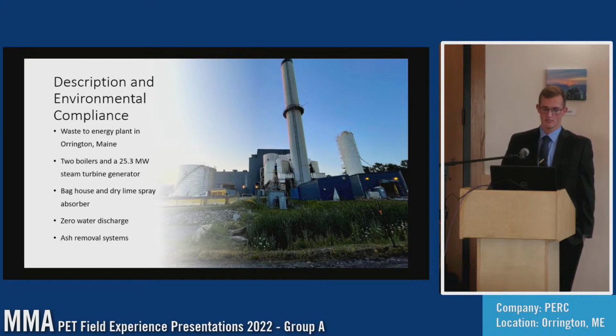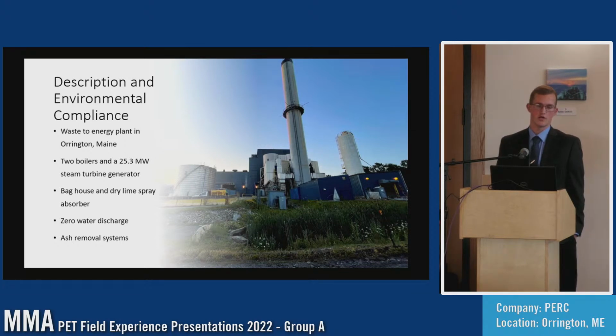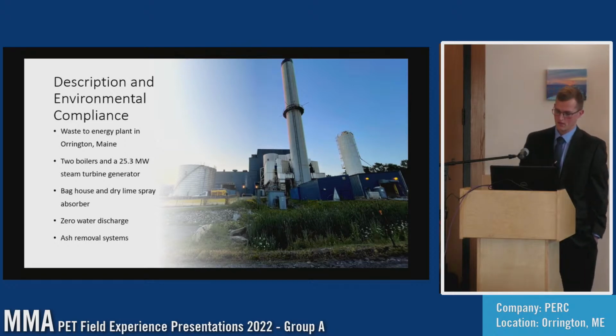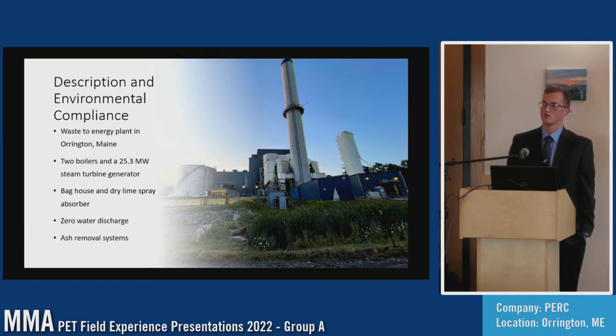PERC uses a baghouse and a dry lime spray absorber to help reduce emissions. The baghouse is mostly for particulate matter, and the dry lime spray helps lower the SO2 emissions. PERC is also a zero water discharge facility as of 2014 and releases no water into the Penobscot, which flows directly alongside the plant. They also use many ash removal systems, which are just conveyors, and bring it all to a trailer that is brought to Juniper Ridge landfill.